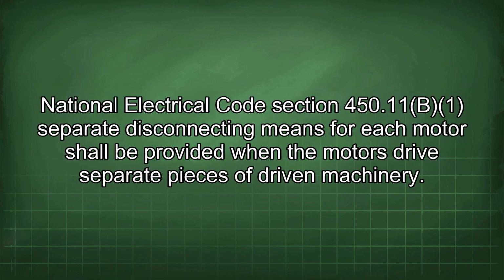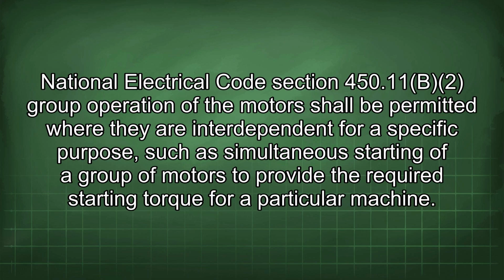National Electrical Code Section 450.11 requires that a separate disconnecting means for each motor shall be provided when the motors drive separate pieces of driven machinery. National Electrical Code Section 450.11(B)(2): group operation of the motors shall be permitted where they are interdependent for a specific purpose, such as simultaneous starting of a group of motors to provide the required starting torque for a particular machine.